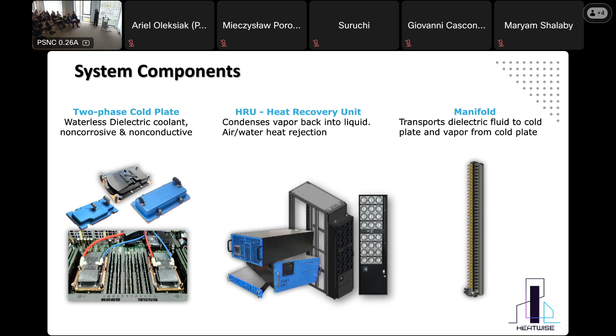At the data center level, you can have reduced CapEx since you need less equipment for cooling, and OpEx stays low because maintainability has no issues. For instance, with water you have to make sure it's balanced and maintained a lot, ensuring no biological growth and that the chemical balance is fine. When using the dielectric liquid, there's no need for that.